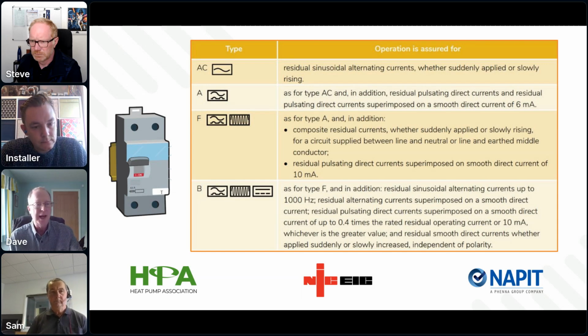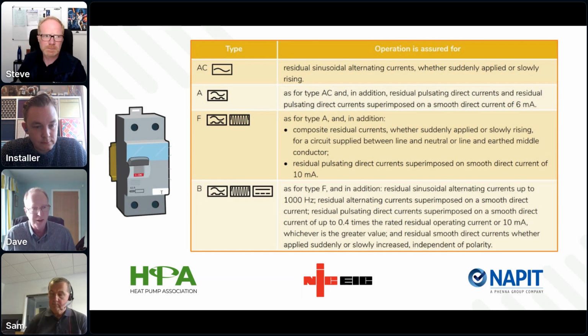and that's an allusion to this type B HP enhanced type B, because the manufacturer or manufacturers who specify it have looked at the frequencies occurring within their appliances, and they've come up with a very specific characteristic where they recognize that it's not any type B, it's this particular type B that they want to specify, and that's why BEMA have added that to their guidance. But yeah, so there's that going on.